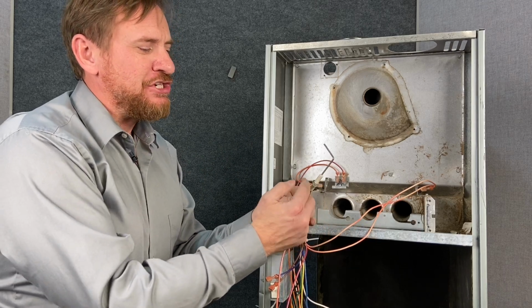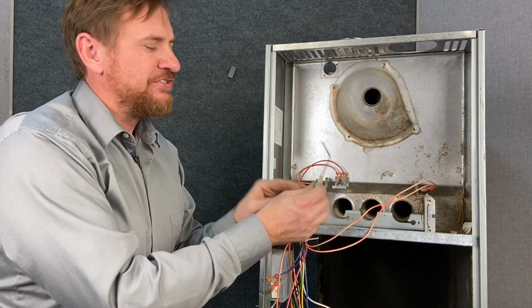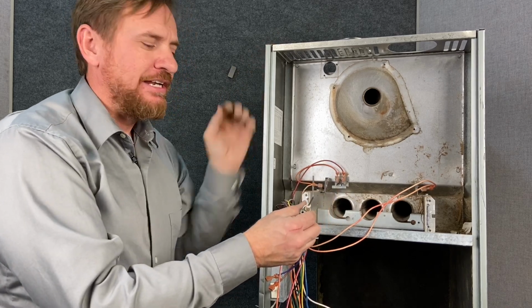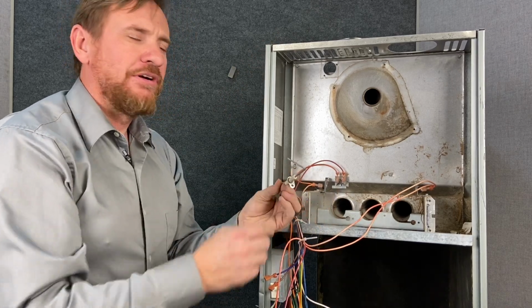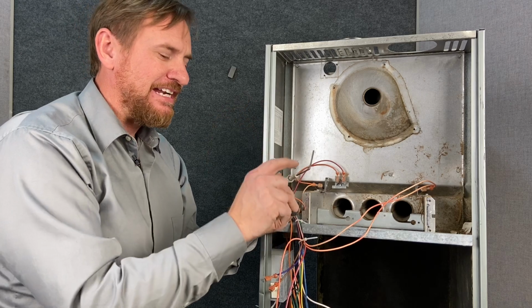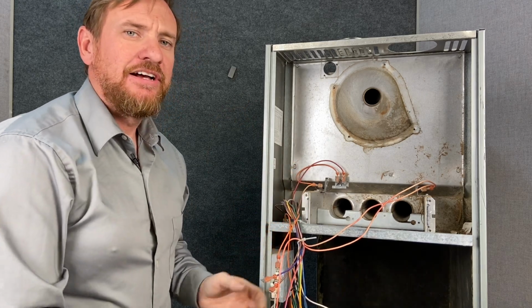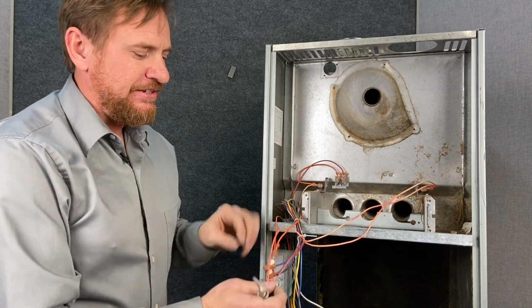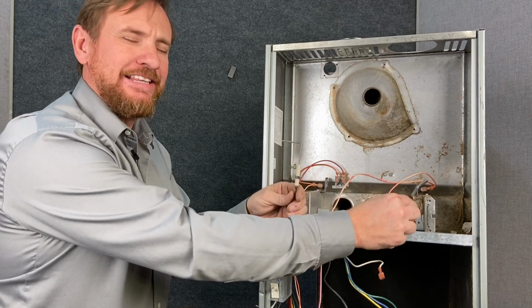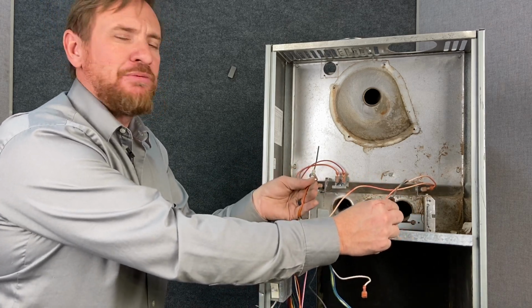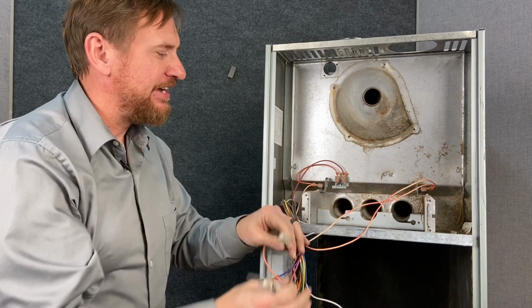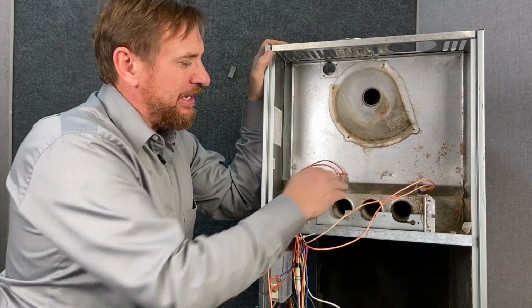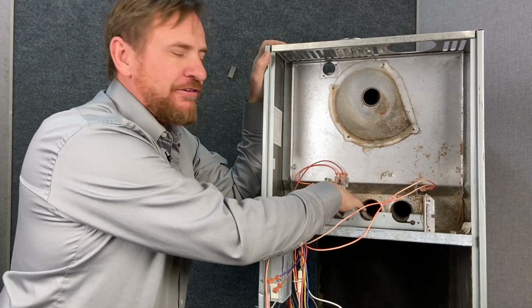But again, the same thing, we check the porcelain, we make sure this connection's good, and there's several ways of checking these we'll get into later, but that's the most important on the maintenance of this furnace, is cleaning that flame sensor and cleaning that spark igniter. So these two components, one's on one side, we ignite the flame on one side, we check to make sure we have a flame all the way across on the other side. Now that we have that out of the way, we can see the tubes for each of our burners.